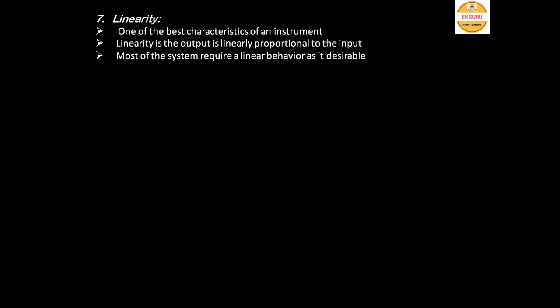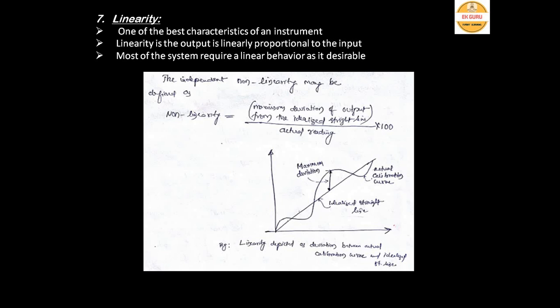Linearity is one of the most important characteristics of an instrument. The output should vary linearly with respect to the input. For an instrument, instead of linearity they often represent the non-linearity at particular points. Non-linearity is defined as the maximum deviation of the output from the idealized straight line, divided by the actual reading, multiplied by 100.